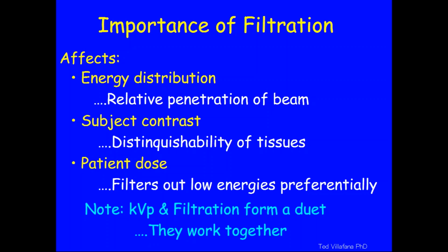But notice the little note I have at the bottom of the slide. KVP and filtration, it's very hard to separate one from the other. In practice, they always come together. They always form a duet. You can affect energy by playing around with KVP, and you can affect energy by playing around with filtration. So, for instance, theoretically, if I go up in KV to increase my energy, I can take out filtration that'll exactly match that increase in energy.